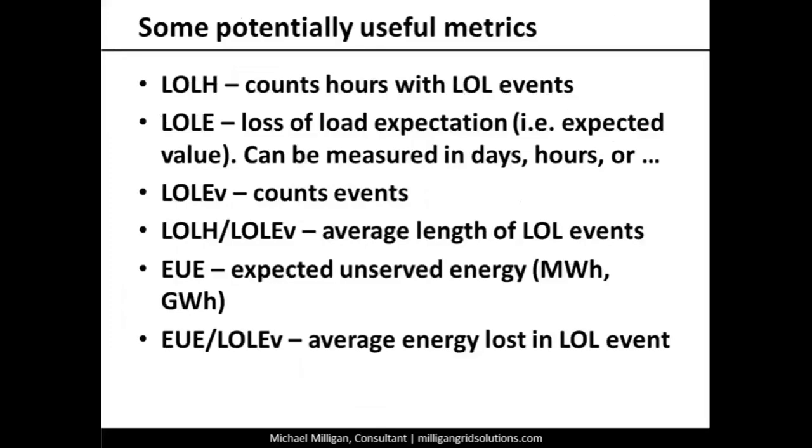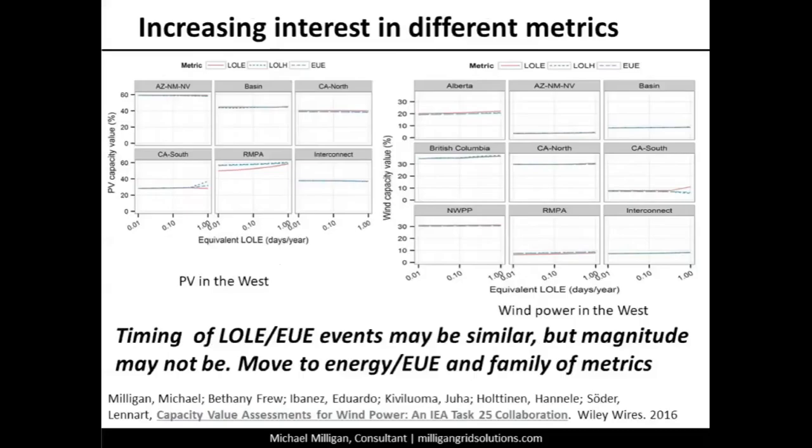So here are some thoughts. Loss of load hours, a number of hours that you have a loss of load event. We're seeing a lot more interest in that. Loss of load expectation, I just talked about that. Could be in days, hours, whatever. Loss of load events counts the number of times, number of events. We could do things like calculate loss of load hours divided by the loss of load events to find the average length of our problems. Expected unserved energy, measured in energy units, megawatt hours, gigawatt hours. And we could do things like calculate the average energy lost in a loss of load event by taking EUE and dividing it by the loss of load events.